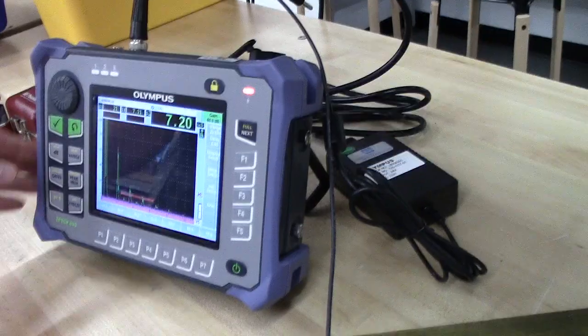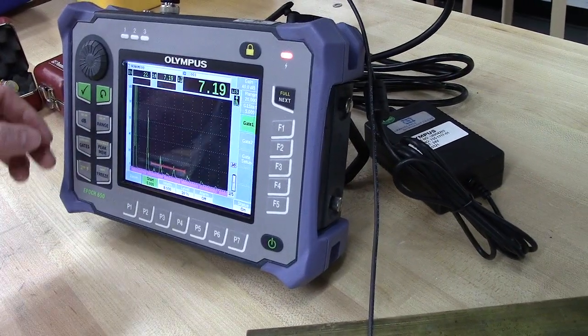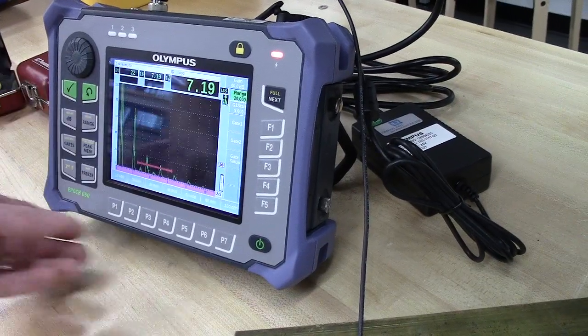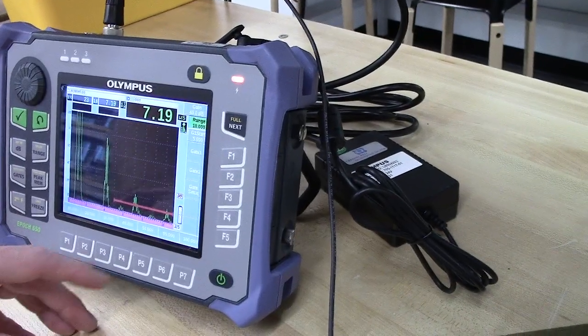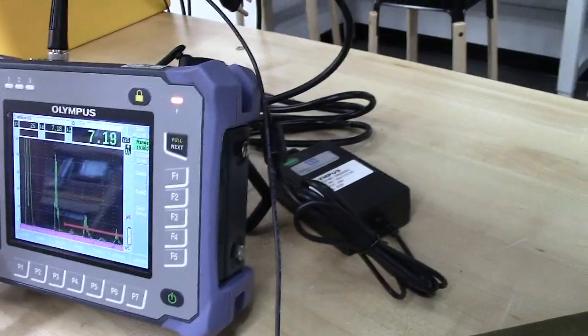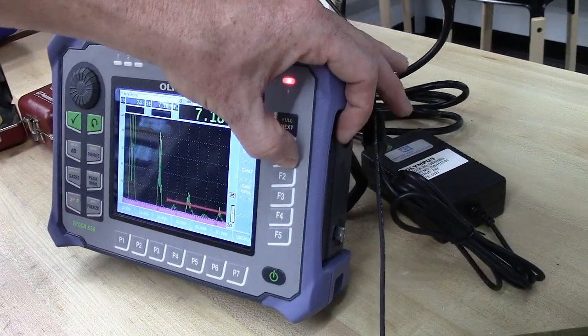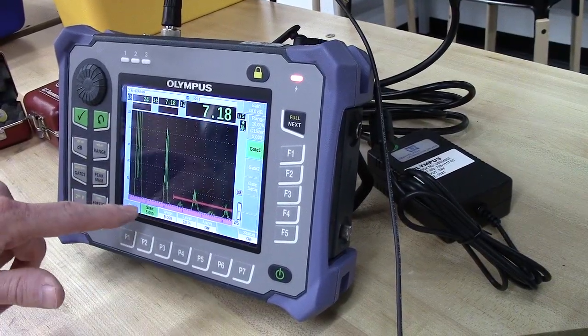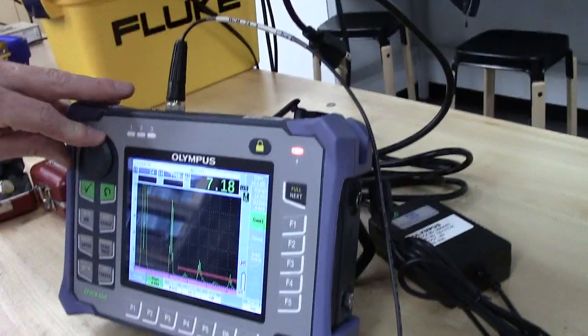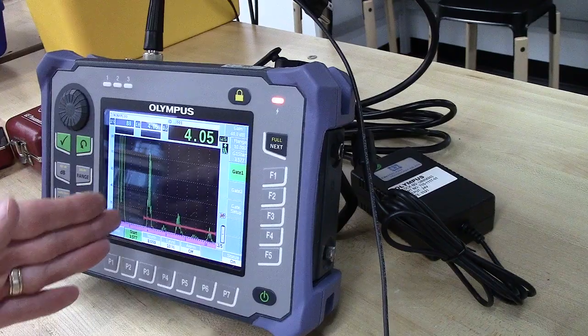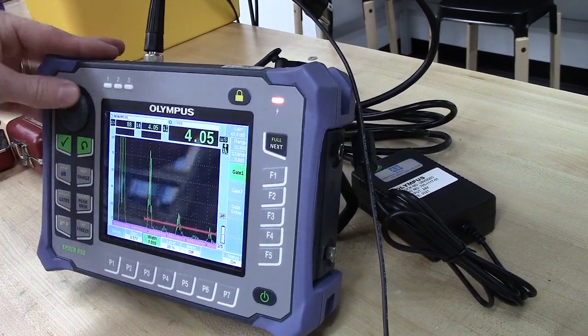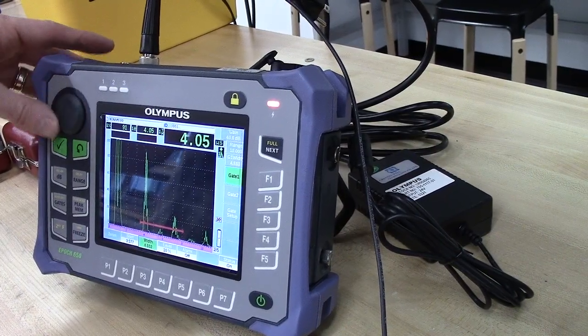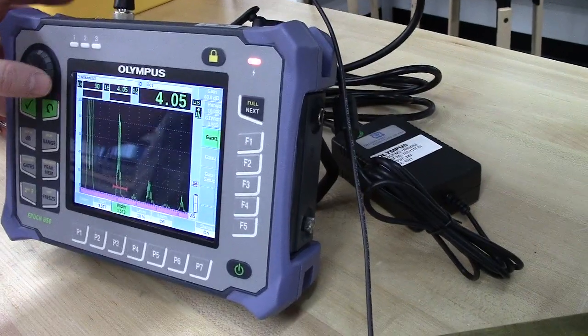So here's the gate button. And maybe we can even zoom in a little bit better on our X axis too. So it's the wrong way, like that. So our first gate is this red bar. Or we can come over, actually pick that gate function to get here. We can pick gate 1 here. And then we can adjust where it starts and how wide it is. So we want to capture, here I'm moving the start to earlier in time. And I want to reduce the width of it now. So we're just capturing that echo.